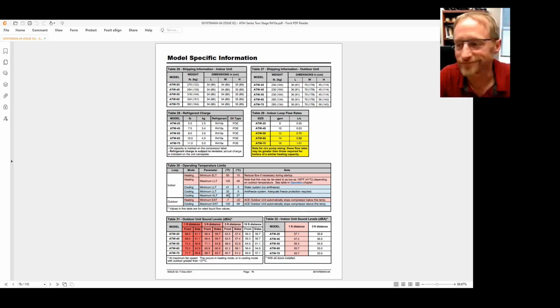Well, I'm not looking at doing something in Georgia, but in Southern Ontario, we've got this peak cooling load that happens for 2 weeks a year or whatever the period is. It gets hot and humid. Can we cut that down enough to comfortable temperatures without having to put all the cooling in? That's it. Yeah. So you can use those temperatures. You could use that 32 there as a theoretical minimum, and I'd aim for a little bit higher than that, but it's certainly possible to get down there.